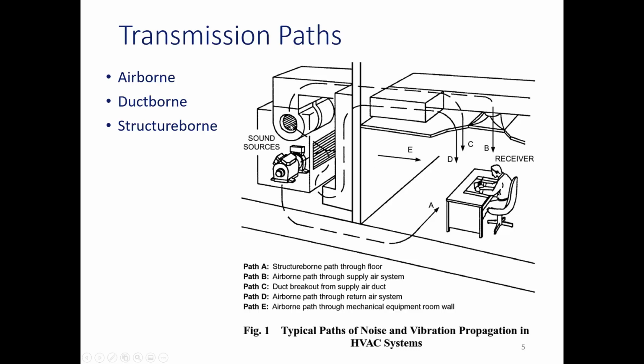Now let me look at this a little more - see the return path. This happens: it's having a return, an open return here, basically using this entire space as a return plenum. So the return path is this one here. This is pretty characteristic of return systems - they have a return ductwork that just punches in above the ceiling of the space and then it just ends, with probably a grill or grills all over in the ceiling.